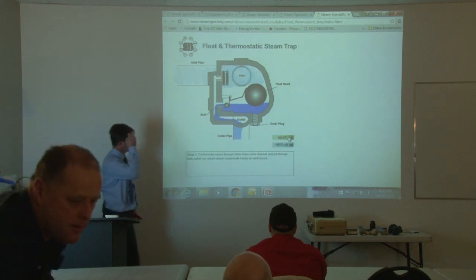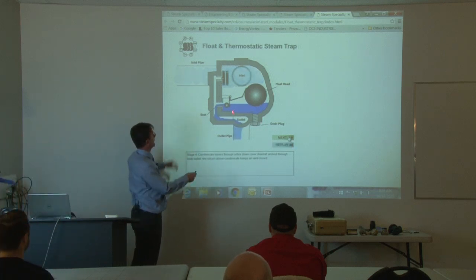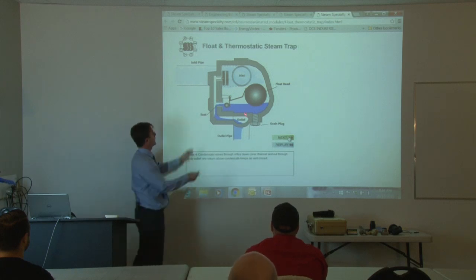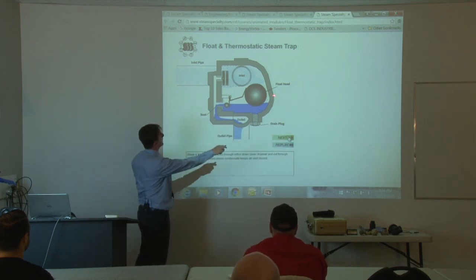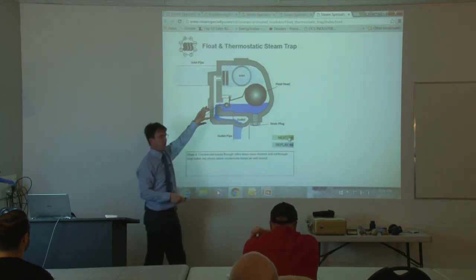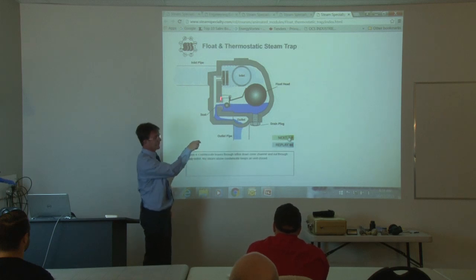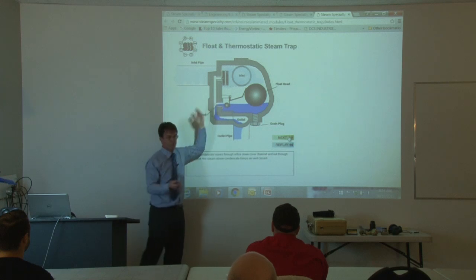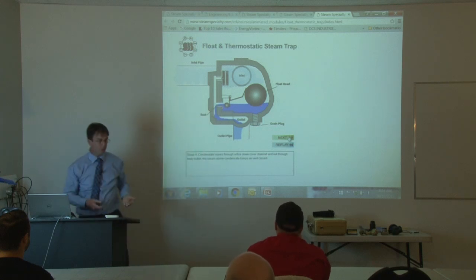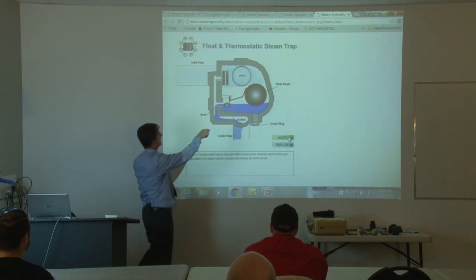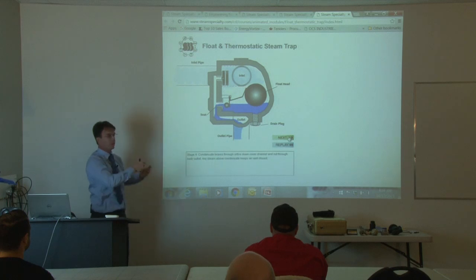One small note about the diagram: it doesn't show that the trap is half full all the time. These traps are designed so there's always some condensate sitting at the bottom, which helps keep steam from passing through the orifice — the head and seat assembly. A repair kit typically includes a float, an arm, an orifice — which is basically a bolt with a hole in it — and an air vent that clips into place.